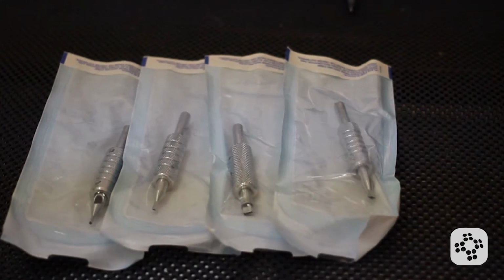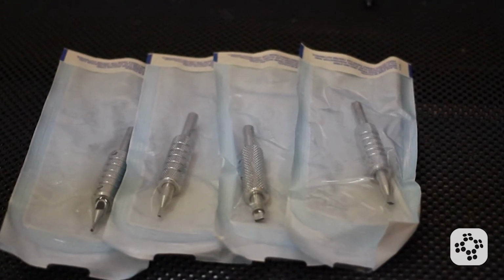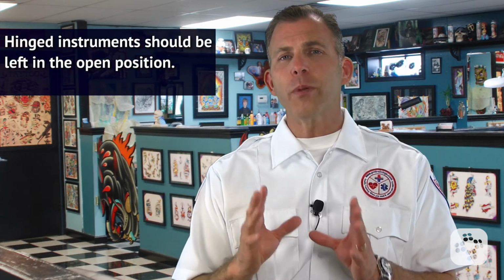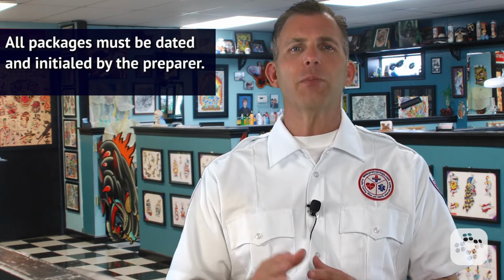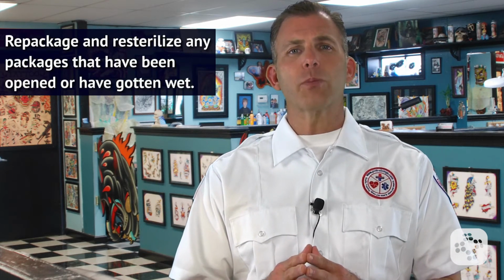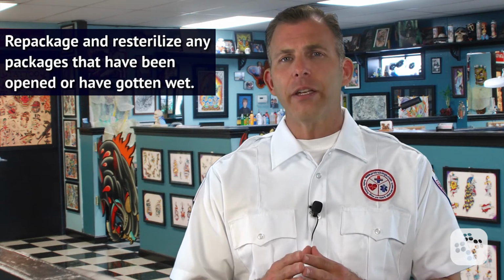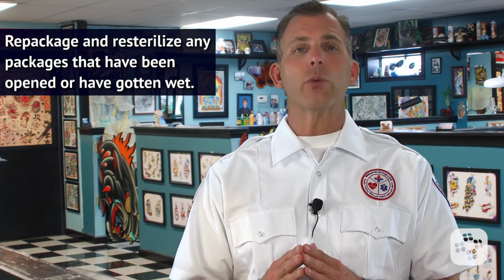Let's talk about packaging for the autoclave. Equipment should be packaged in procedure setup packs with color change indicators, or packaged individually in peel packs with color change indicators. Hinged instruments should be in an open position, and all packages need to be dated and initialed by the preparer. If a sterilized package has been breached or allowed to get wet, the instrument shall be repackaged and re-sterilized before use. Sterilization with an autoclave.